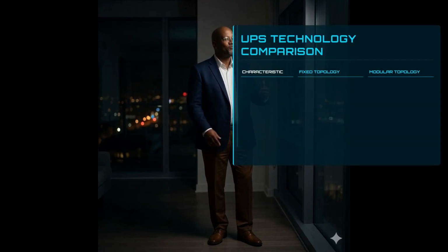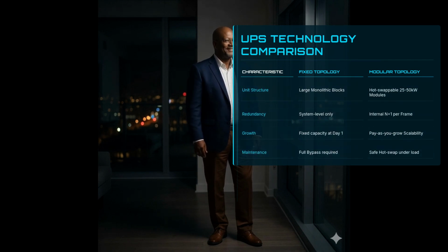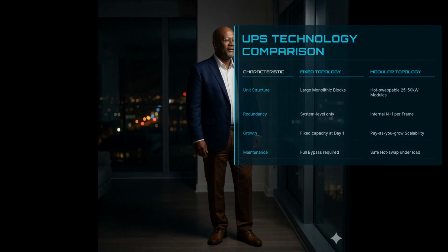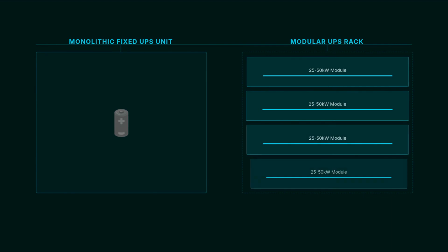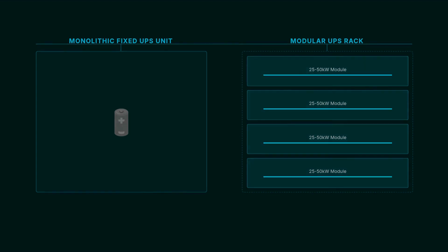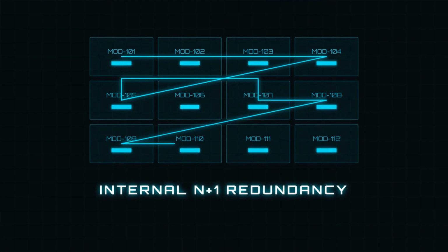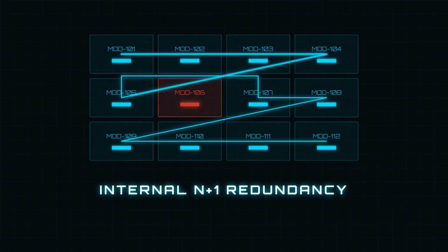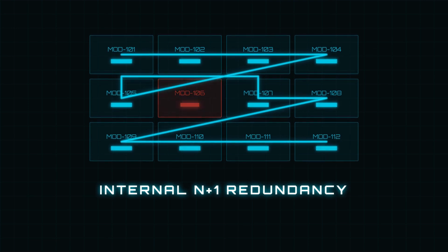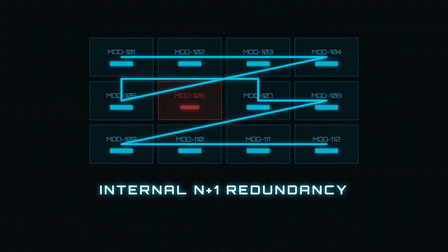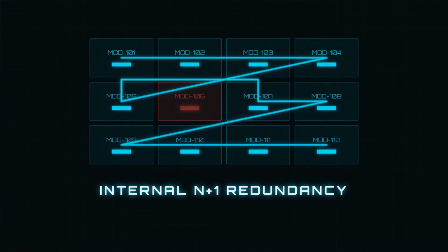At this hyperscale, we've moved away from the fixed topologies used in smaller facilities. Modular UPS technology is fundamentally different, offering scalability and what we call redundancy in redundancy. It is a smarter way to manage power. A fixed topology uses large, monolithic units. In our modular topology, we use racks of plug-in power modules, typically 25 to 50 kilowatts each. This allows us to treat power like a modular IT component, providing flexibility we've never had before. While fixed systems have redundancy at the system level, modular systems provide N+1 redundancy inside each individual UPS. A module failure only auto-bypasses around itself, while all other modules continue to support the load without a ripple.